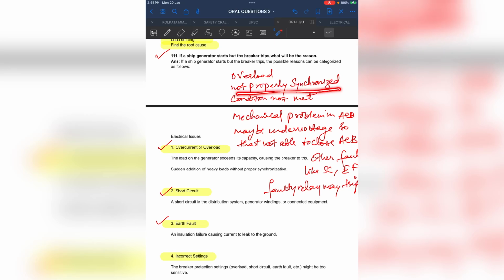If they are not properly synchronized, the generator breaker will just close, and after that it will trip. If the condition is not met, there can also be an overload, because when you close the breaker, suddenly too much load is connected to the generator, and due to this overload the breaker will trip.